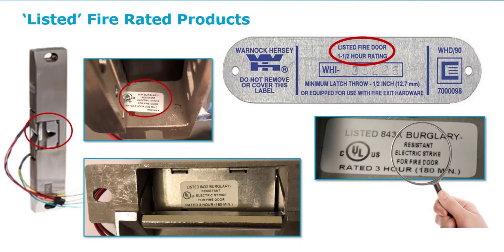You have to pull a permit for it. The work should be tested and inspected by another party to confirm the workmanship is done neat and clean. The products we're installing also have to match the rating of the frame. If I've got a frame rated for three hours, the product I install must also be rated for three hours. I have to match what the existing frame is.